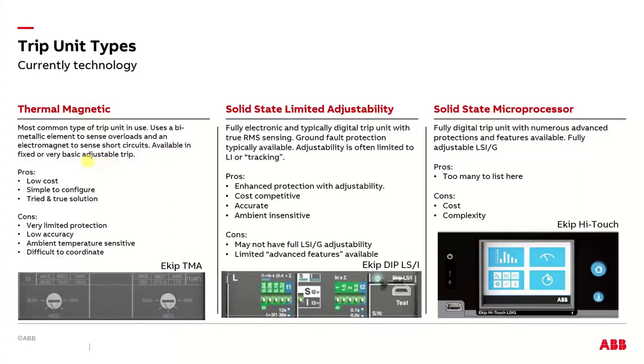And let's see here. The common things that they have are 2 components to it. Obviously, a thermal component, and that's usually a bimetallic strip that heats up and bends to cause the breaker to operate. And that basically looks for overloads. And then there's a magnetic element, and if you exceed a certain amount of amps, it'll pick up immediately. So that's your instantaneous protection in the magnetic part. So thermal is your time delayed, magnetic is your instantaneous. The pros are very low cost. They're simple to configure. Most of the time, there's no dials or adjustments available. Tried and true. They've been around since the beginning of time. The beginning of electricity, I guess.